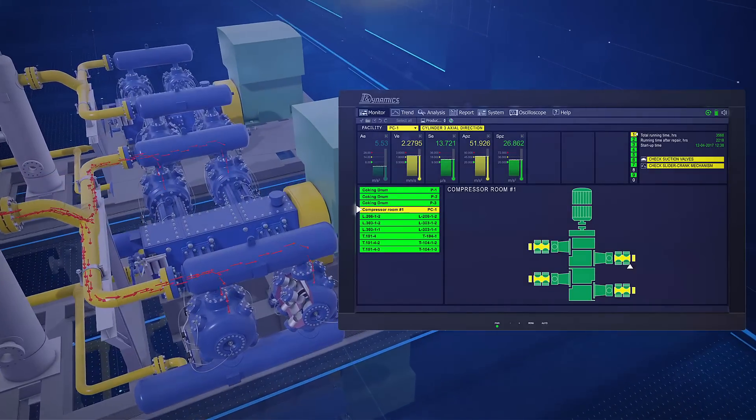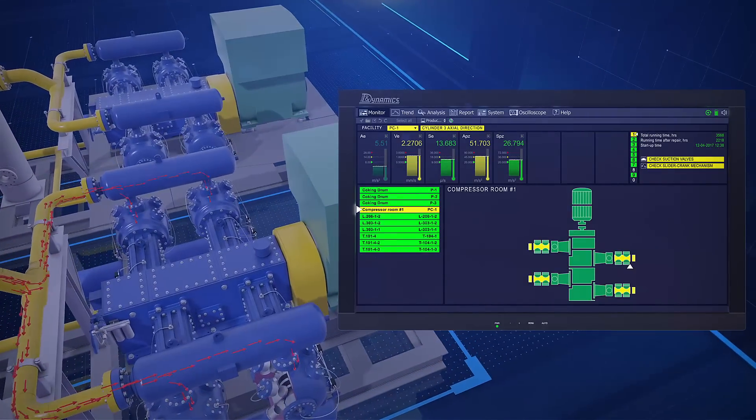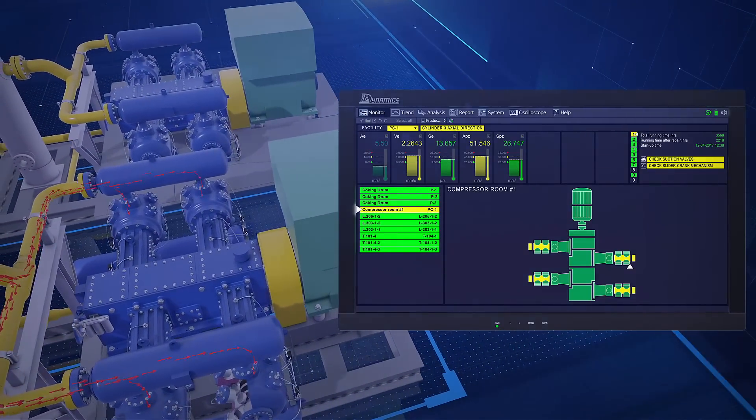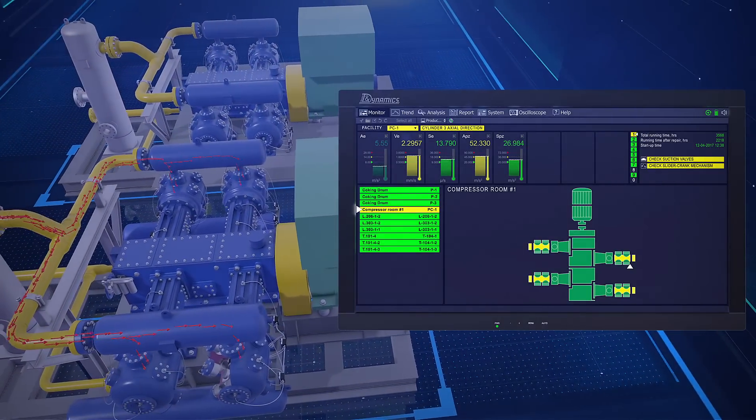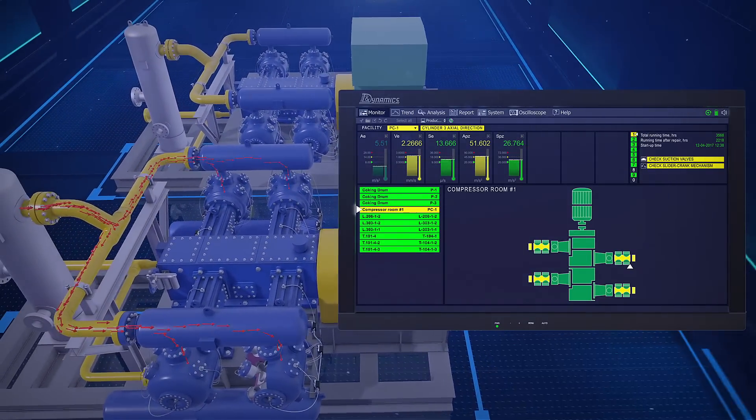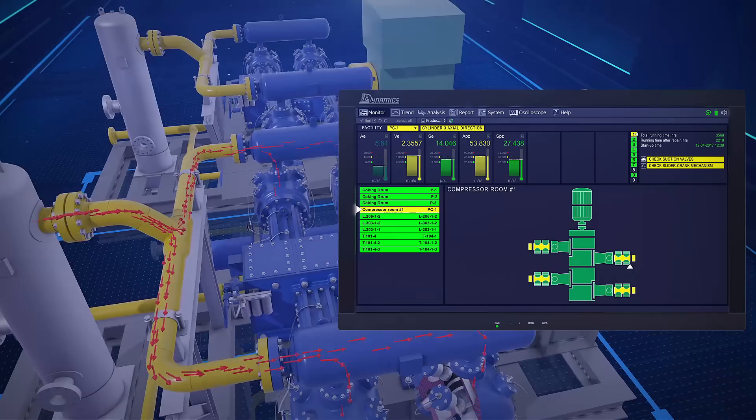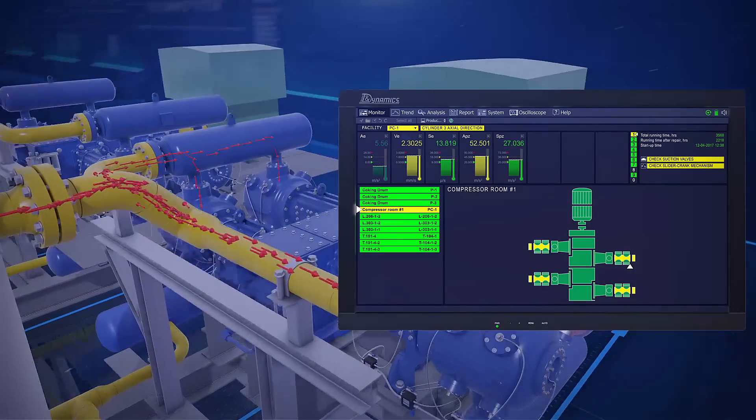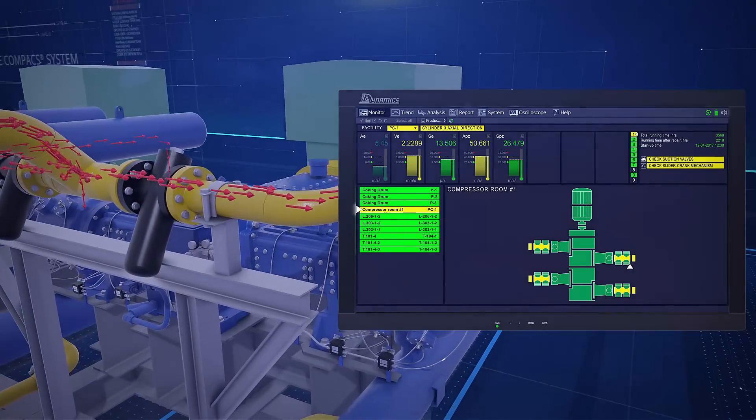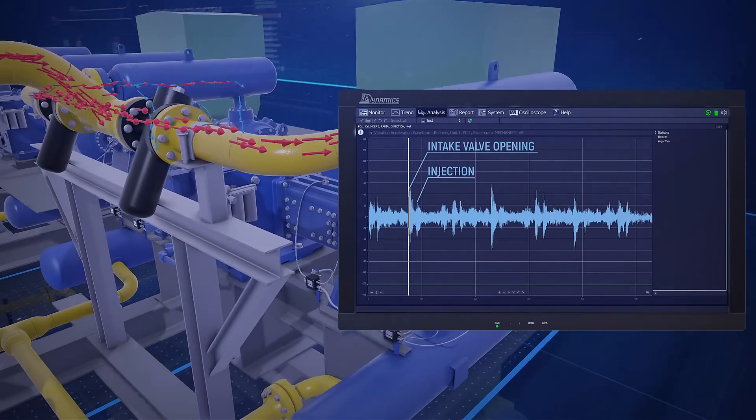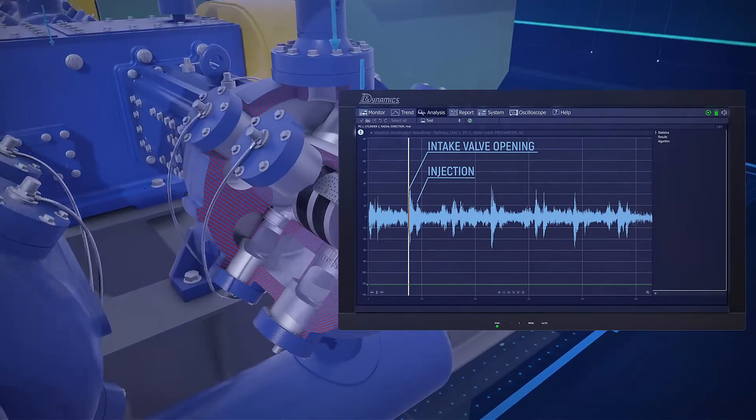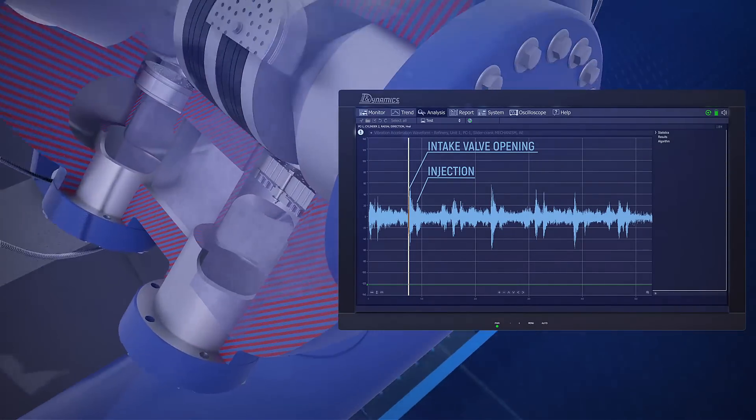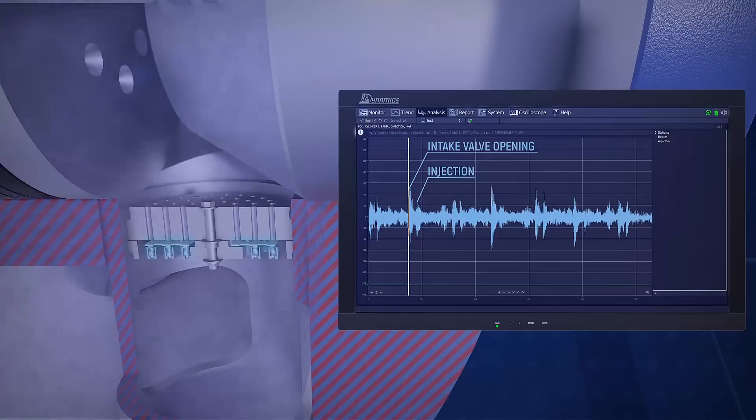They kept two standby piston compressors to keep the facility continuously running. The compressor was repaired once a week until a gas filter was installed. Since the filter was installed, the issue no longer was a bottleneck for the unit.